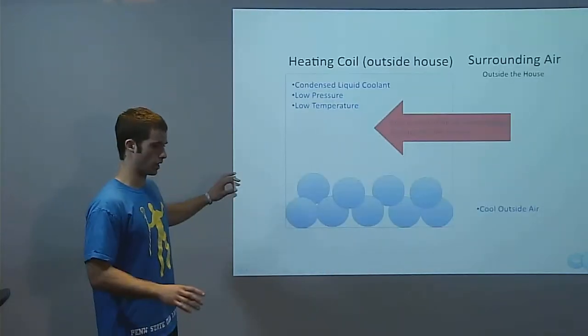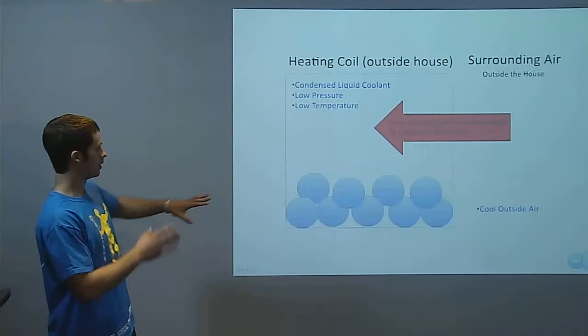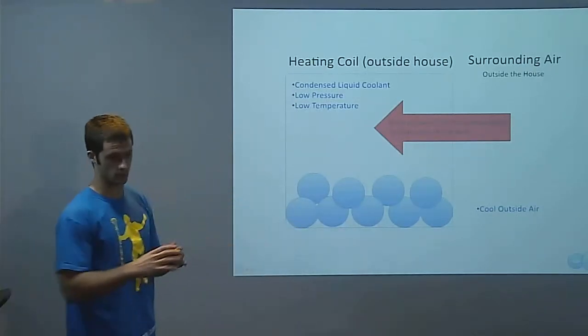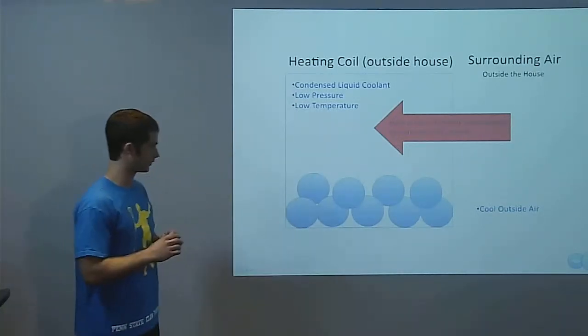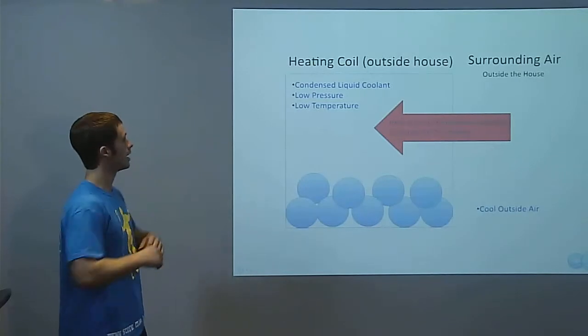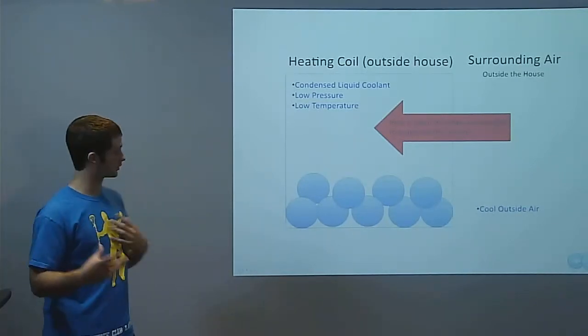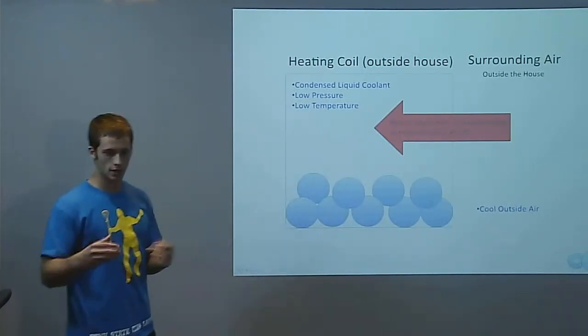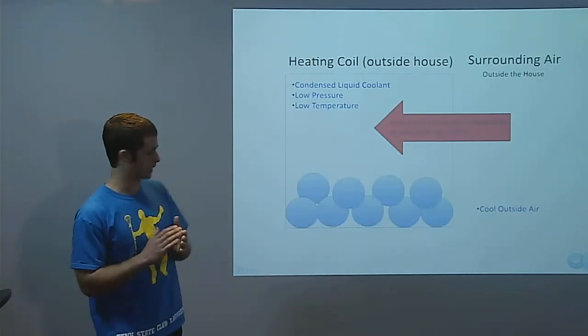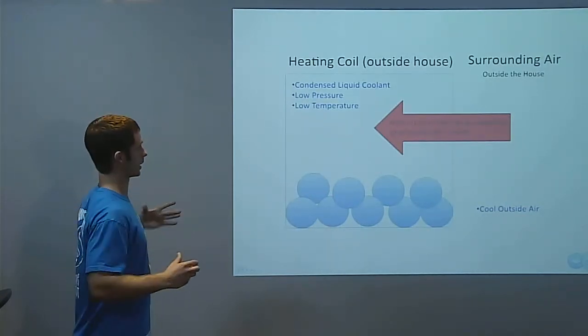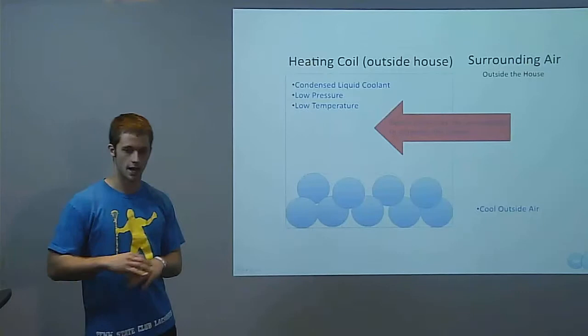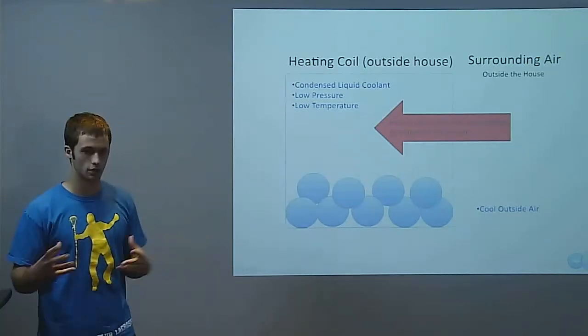On a more molecular level, this coolant will pass through an expansion valve, and what that expansion valve does is it takes a liquid coolant and lowers the pressure, also lowering the temperature. Because now this coolant has a low pressure and a low temperature, it wants to evaporate. So what it'll do, even outside in cold temperatures, is it will draw heat from the outside surroundings in order to evaporate this liquid coolant into a vapor.